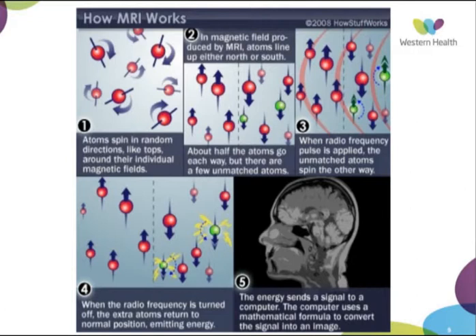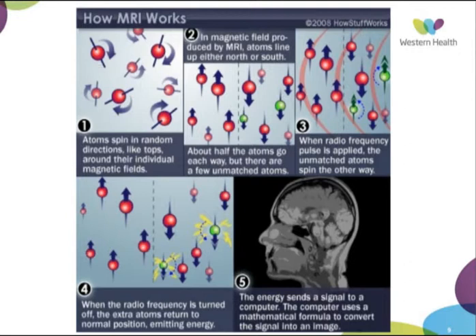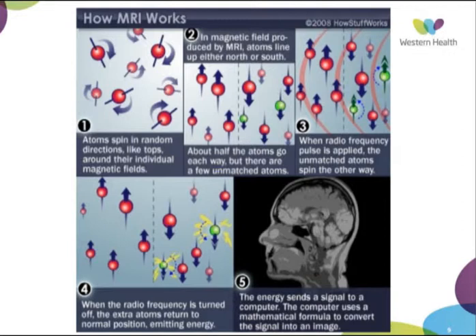The strength of the magnet is measured in Tesla units. At Western Health, our scanners are 3 Tesla and 1.5 Tesla. A higher magnet produces better quality, however the lower field machine allows some metals to be used. With the 1.5 Tesla magnet, some metalware such as pacemakers can go through, whereas with the 3 Tesla, they're not permitted. With MRI we look at two different sequences: T1 and T2, relating to repetition time and echo time. With T1, fat and bone marrow are bright. With T2, joint fluid and blood vessels are bright. Depending on what we're looking for, we'll look at the varying sequences.